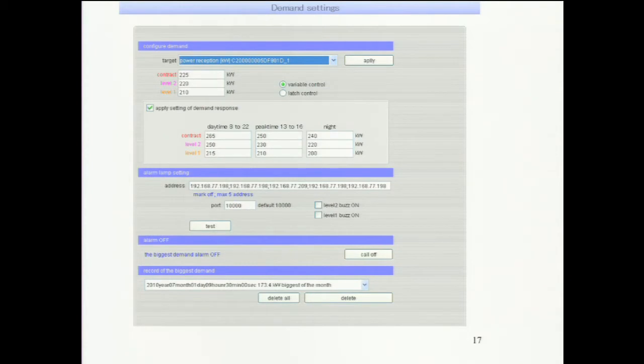This is another screen for setting threshold levels. You'll notice in the middle there's a contract—most electric contracts have demand contracts, so you're not supposed to exceed a certain amount of demand. That's because the actual power line connected to your factory has a capacity, and you don't want to exceed it or things will burn or melt. Also, having a demand contract implies supply-side planning on the utility side, and you shouldn't exceed that planned amount since that's what utilities have planned for in purchasing energy. So there's a contract level, and you never want to go over it, meaning you have levels at which you want to initiate action.